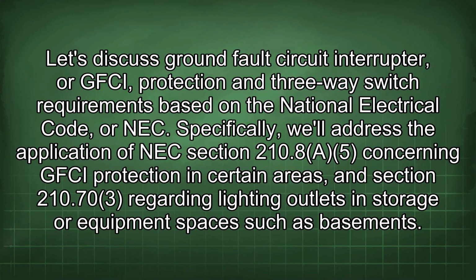Let's discuss ground fault circuit interrupter, or GFCI, protection and three-way switch requirements based on the National Electrical Code, or NEC. Specifically, we'll address the application of NEC Section 210.8 concerning GFCI protection in certain areas, and Section 210.70(3) regarding lighting outlets in storage or equipment spaces such as basements.